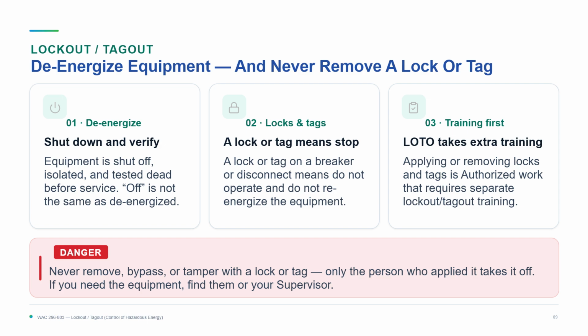When equipment is serviced, it gets de-energized, isolated, and locked or tagged out, so it can't start unexpectedly. As an unqualified worker, you are an affected person. You may operate or work near the equipment, but you never apply or remove a lock or tag. Doing that is authorized work that takes separate lockout-tagout training. If something you need is locked out, find the person who applied it or your supervisor. Never work around it.